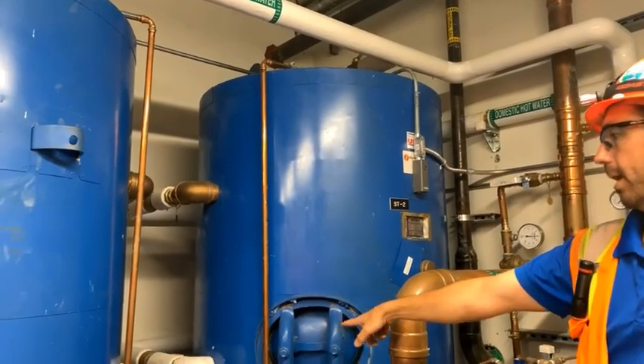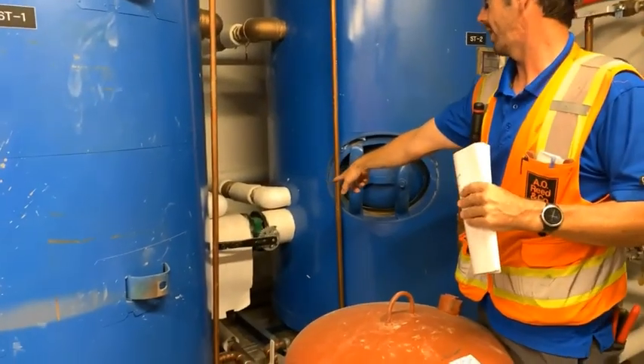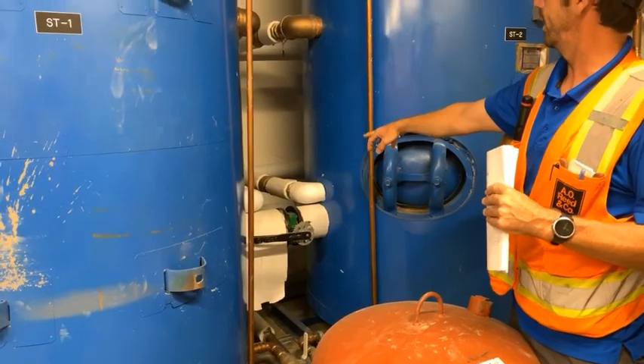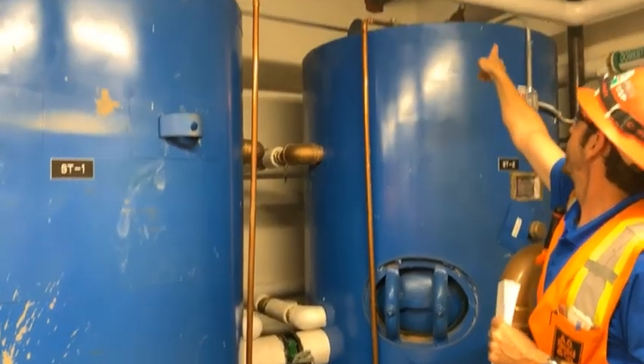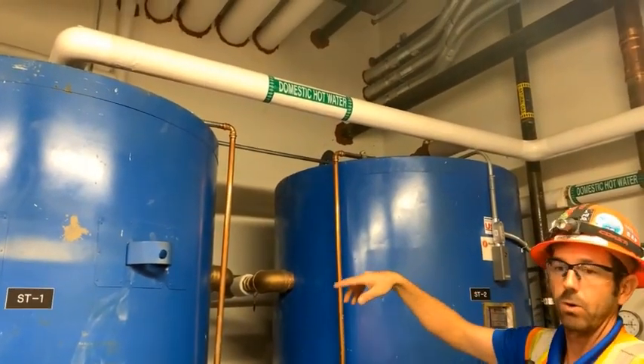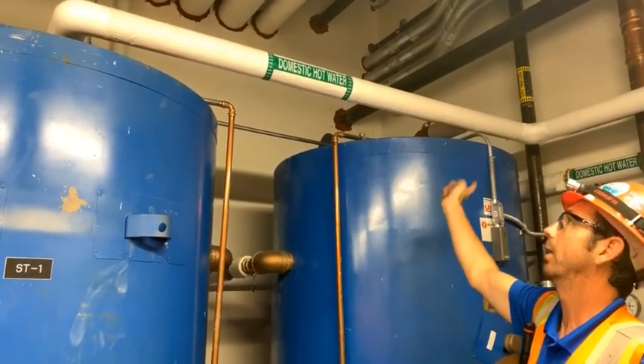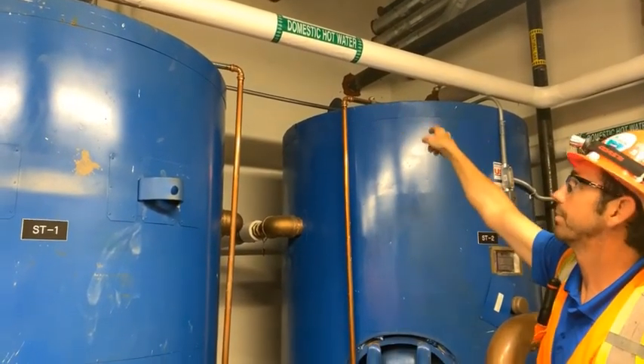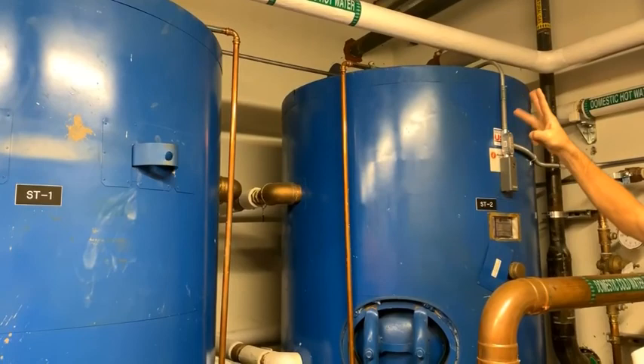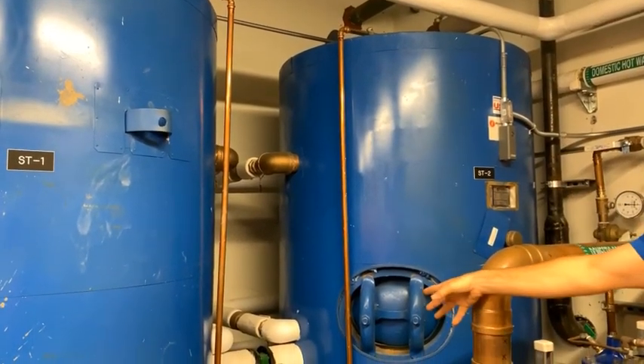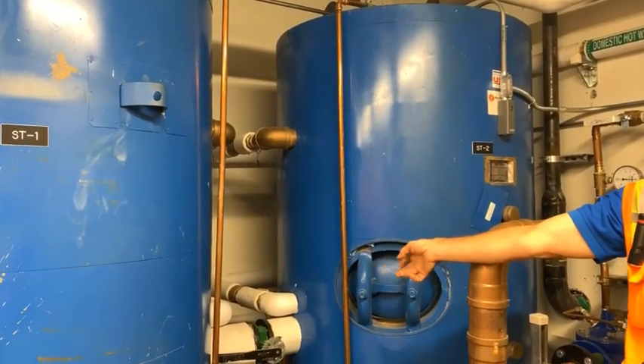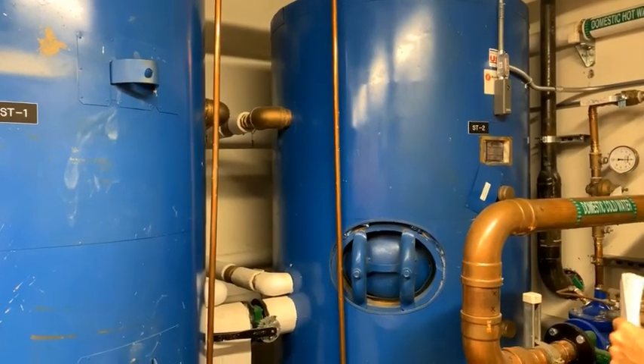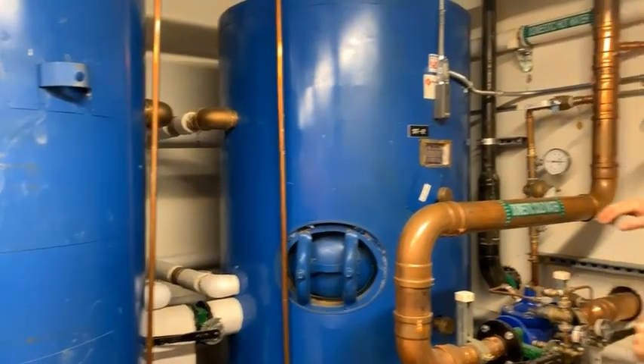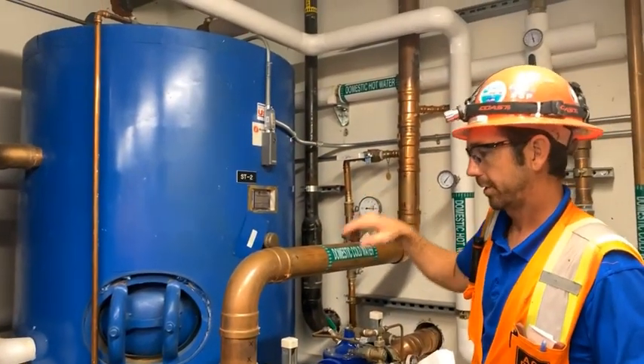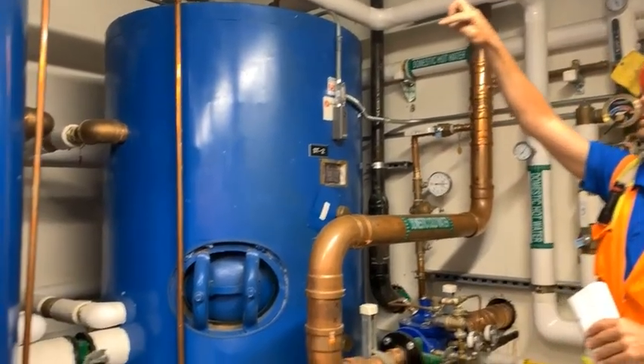There's an equalizer line in between the tanks. That's this one right here. And each tank has an inlet and an outlet, and an in and an out for the heat exchanger loop, and then an outlet to the mixing valve at the top. So there's 3 shutoff valves per tank, and then each tank will share the isolation equalizer line, okay? There's drains at the bottom, pressure release at the top.